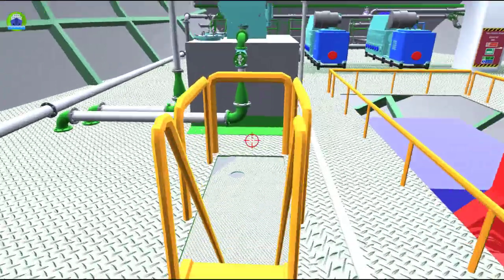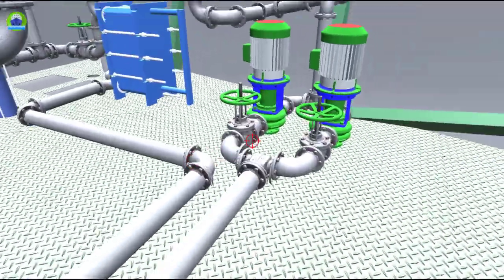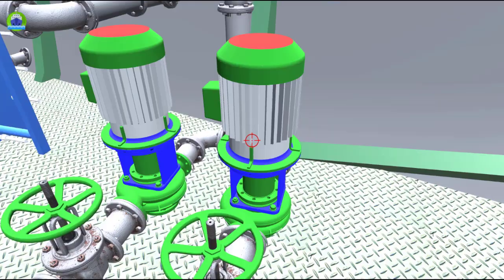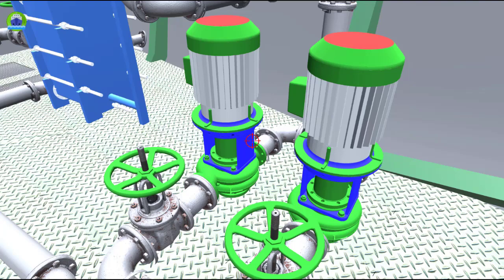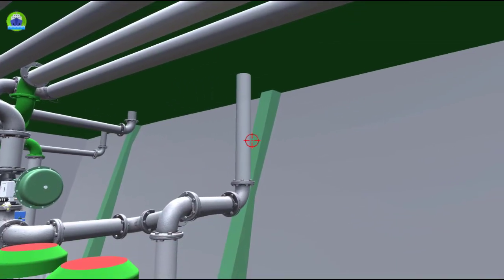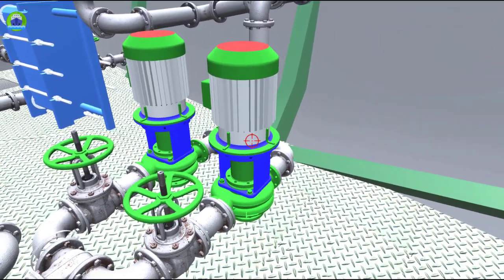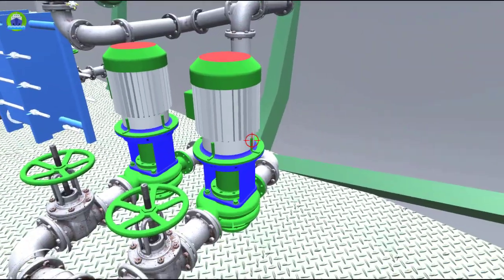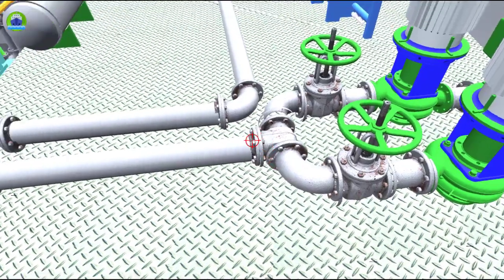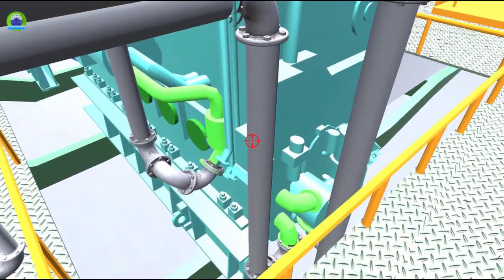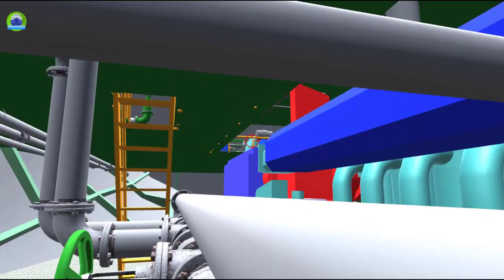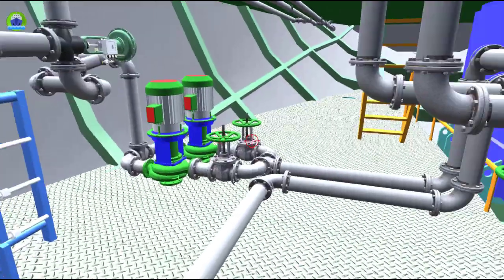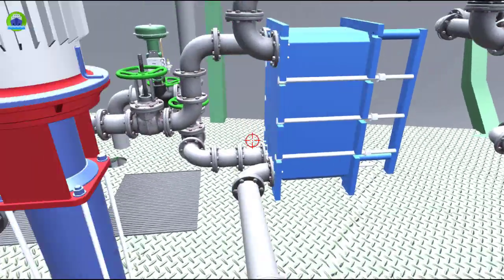That's the fresh water generator as we pass by. Here are the CFW jacket cooling water pumps — there are two of them, and some ships also have additional substitute pumps in case of maintenance or other issues. That pipe comes from your cooling water expansion tank. It draws out the water by gravity and goes to the centrifugal radial type pumps, which then supply the main engine. It draws out heat from the main engine, which produces tremendous heat. The water goes out and some goes back to your expansion tank, while the rest goes to your jacket cooling heat exchanger.